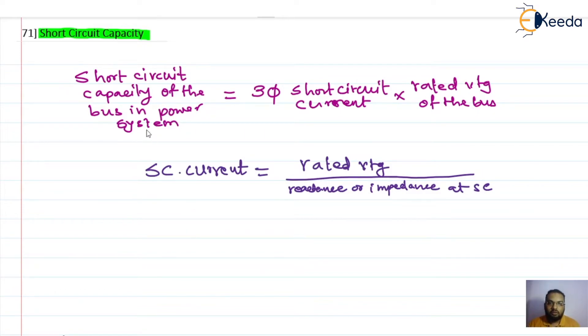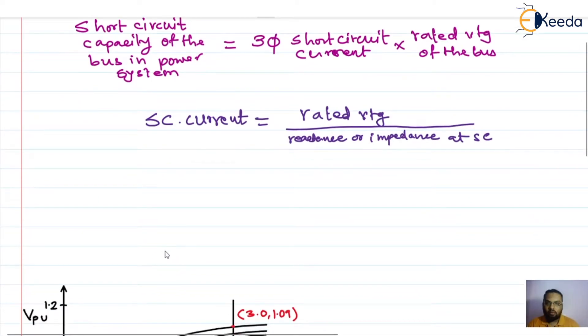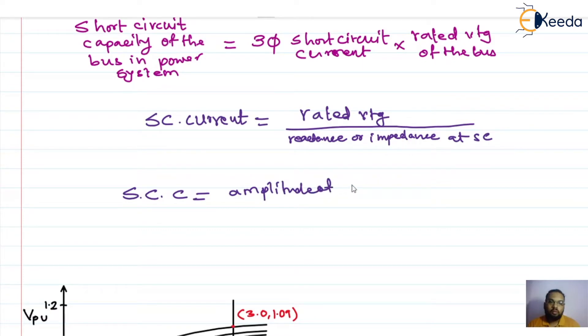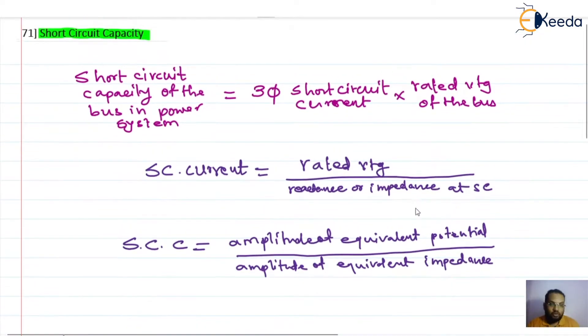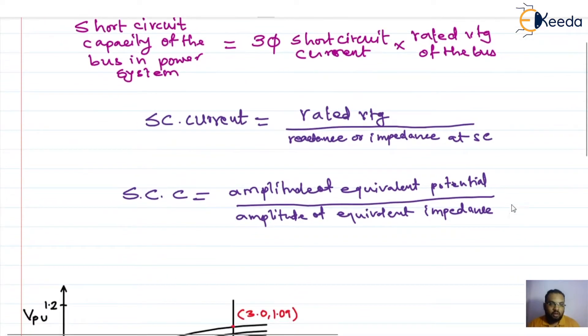As per the definition of short circuit capacity calculation, we can also calculate the short circuit capacity with this formula: it is nothing but the amplitude of equivalent potential divided by the amplitude of equivalent impedance, where the amplitude of equivalent potential is the rated value and the equivalent impedance is at short circuit. These are the basic ways to calculate the short circuit capacity of a bus in a power system.